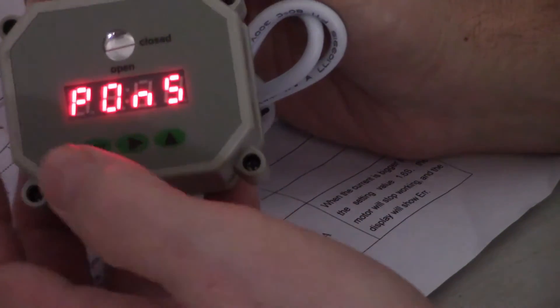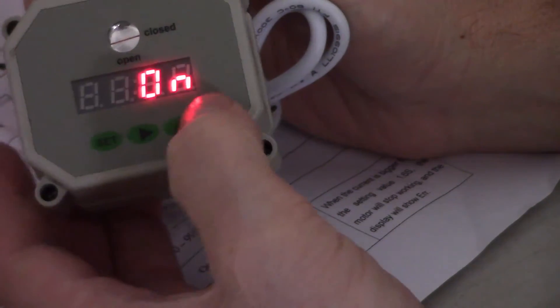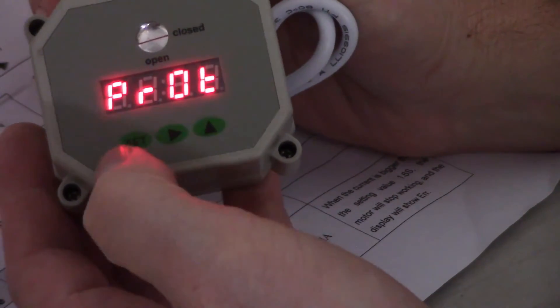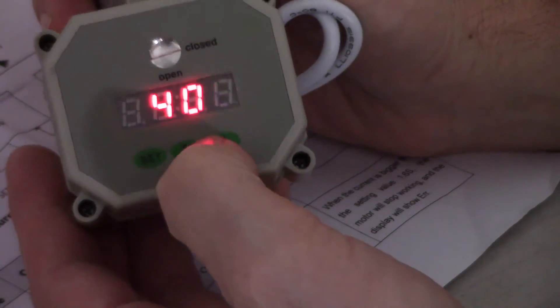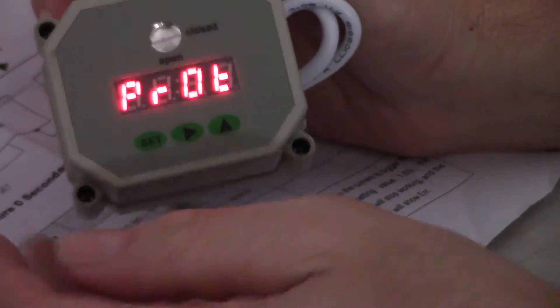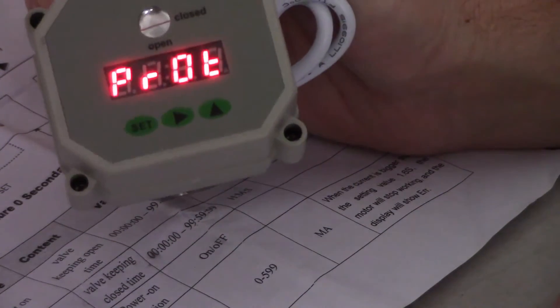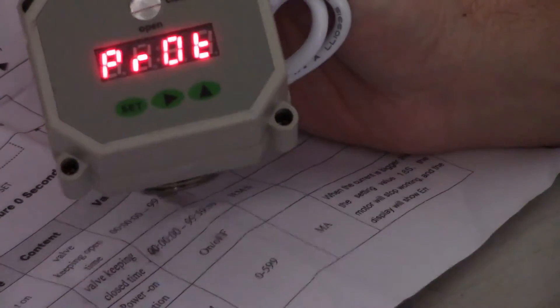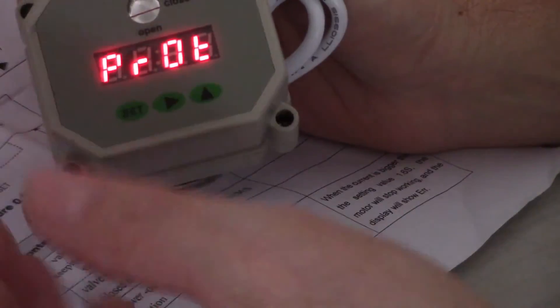You set this, it comes preset to on. Then you go to the next one and it's saying 400, which means it's set for 400 milliamps. It means as soon as it starts trying to draw more than that because something's stuck in there, it'll shut down automatically so it won't wear the motor out.